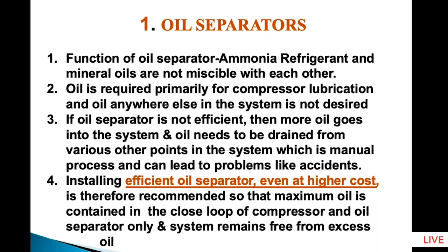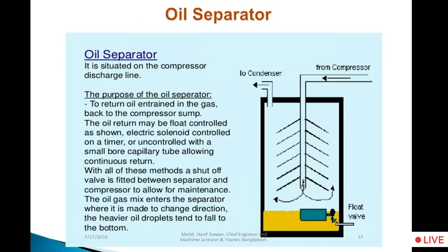Because, as you all agree, it is the refrigerant which does the cooling, and oil has no cooling effect. So if oil is there in the system, the efficiency of the system will drop. So try to keep oil in the system to a bare minimum. Try to control it with a good oil separator. These are the different oil separators, which are of various different efficiencies.